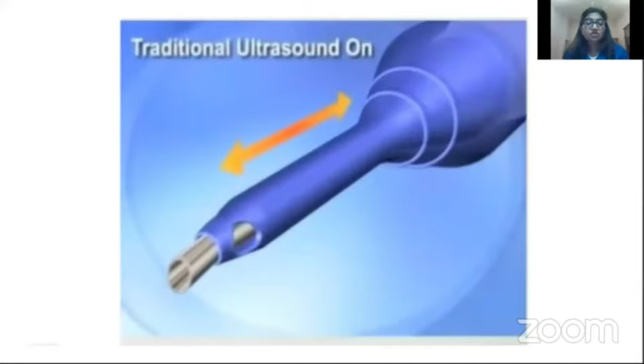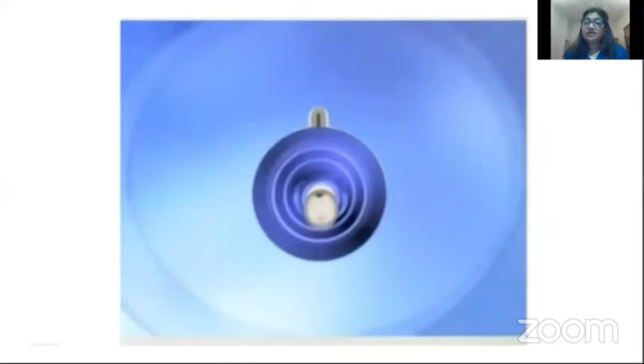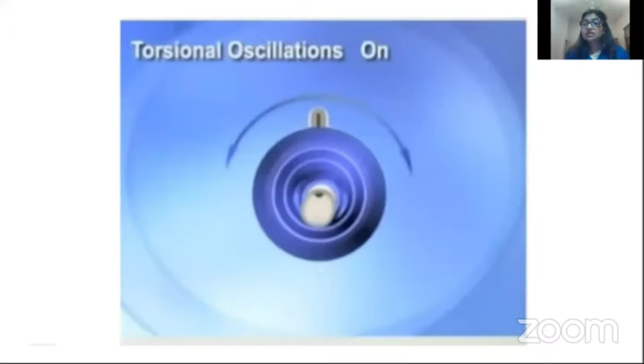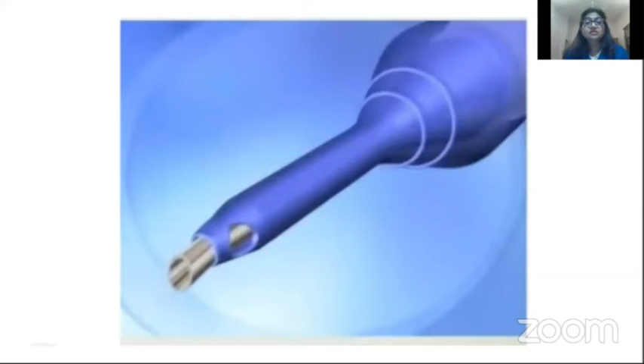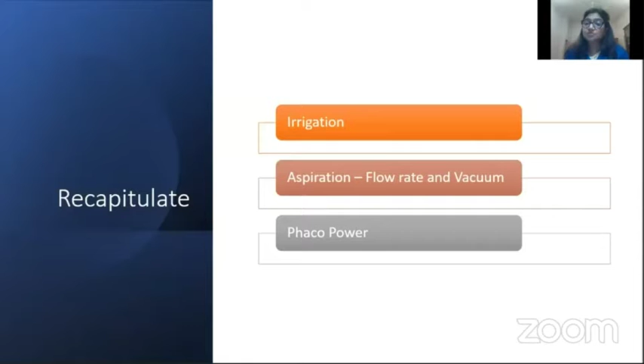And this is how the tip will oscillate in a traditional, which is a longitudinal phaco, but to reduce chatter and turbulence, you can have something like a torsional oscillation, by which it will not push the tip or the fragments away. So to recapitulate, you have the irrigation, the aspiration in the form of flow rate and vacuum, and you have the phaco power to be able to do a successful phacoemulsification.